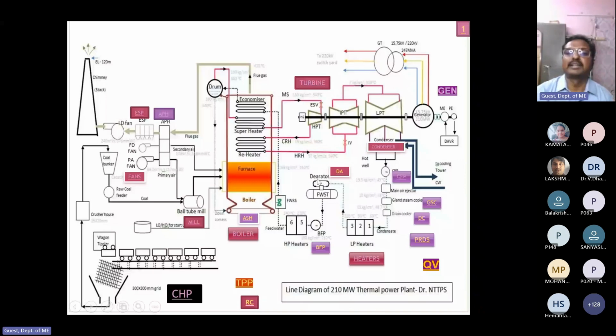Here also, some amount of steam is taken from the turbine and sent to the deaerator, where it is mixed with the water and its temperature increases. So the solubility of gases decreases as the temperature increases. When the temperature of the feed water increases, gases automatically escape from the deaerator.